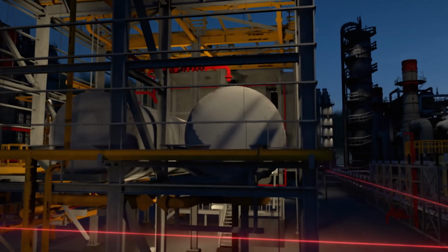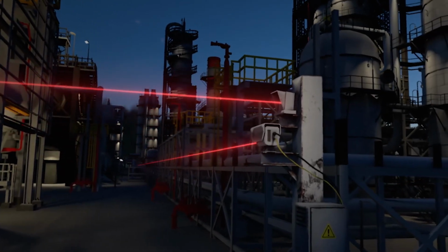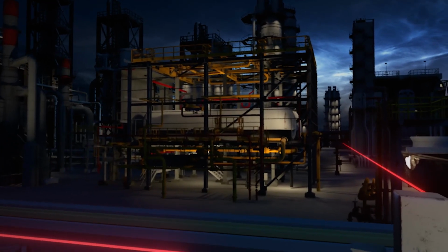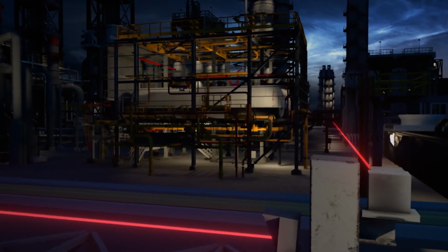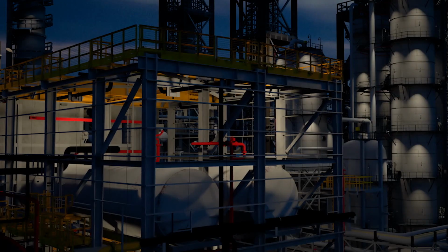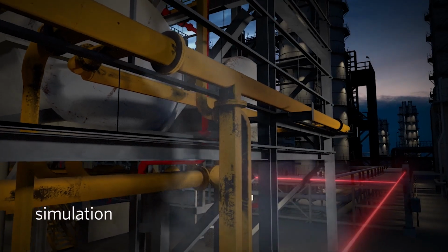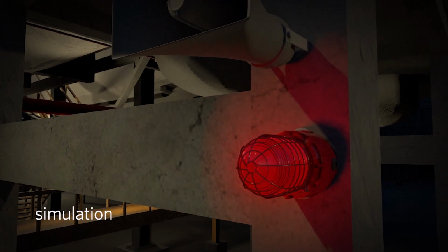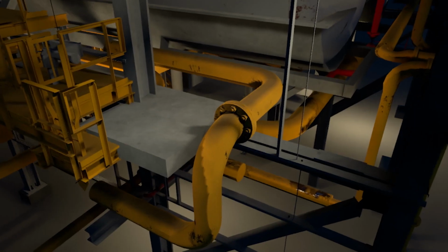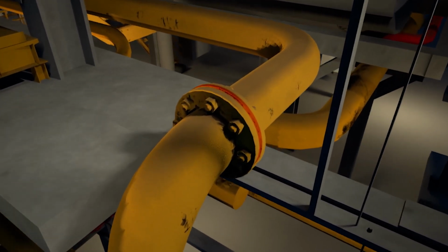Among other tools, refineries stage different types of monitors in and around the HF unit to alert operators in real time that they need to respond following established procedures. Monitors typically include highly sensitive perimeter lasers, point sensors, chemical spot detectors, as well as cameras throughout the unit that provide visual verification. This equipment can detect trace amounts of HF and will trigger visual and audible alarms on the unit and in the central control facilities where the unit is monitored remotely. We even apply a special paint around pipe connections that changes color to indicate that the slightest leak has occurred so that an operator can intervene to prevent an incident.